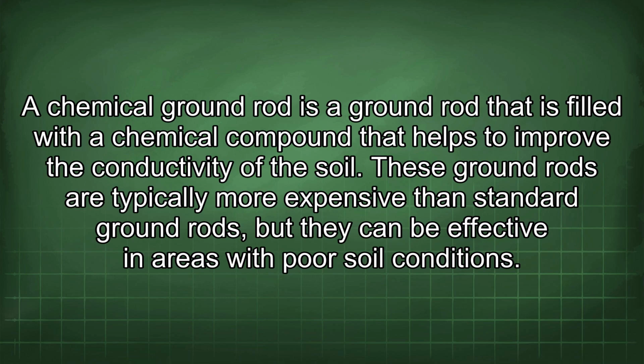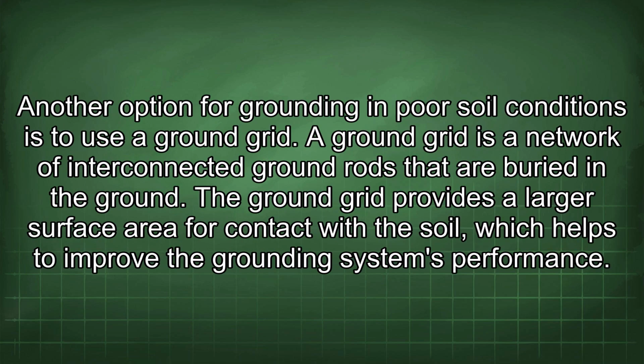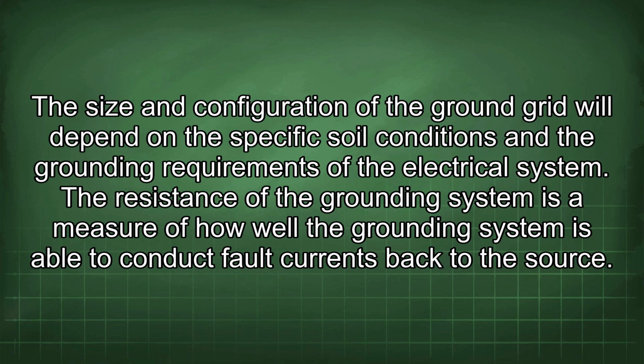A chemical ground rod is a ground rod that is filled with a chemical compound that helps to improve the conductivity of the soil. These ground rods are typically more expensive than standard ground rods, but they can be effective in areas with poor soil conditions. Another option for grounding in poor soil conditions is to use a ground grid. A ground grid is a network of interconnected ground rods that are buried in the ground. The ground grid provides a larger surface area for contact with the soil, which helps to improve the grounding system's performance.